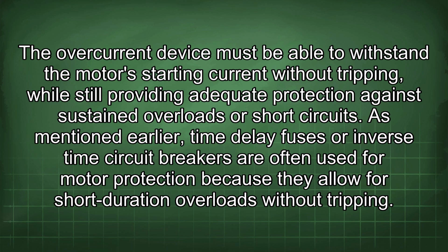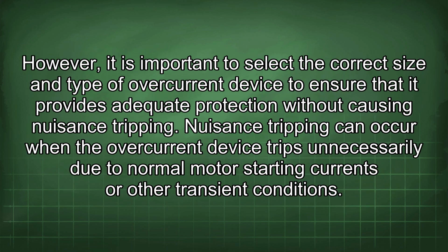As mentioned earlier, time delay fuses or inverse time circuit breakers are often used for motor protection because they allow for short duration overloads without tripping. However, it is important to select the correct size and type of overcurrent device to ensure that it provides adequate protection without causing nuisance tripping. Nuisance tripping can occur when the overcurrent device trips unnecessarily due to normal motor starting currents or other transient conditions.